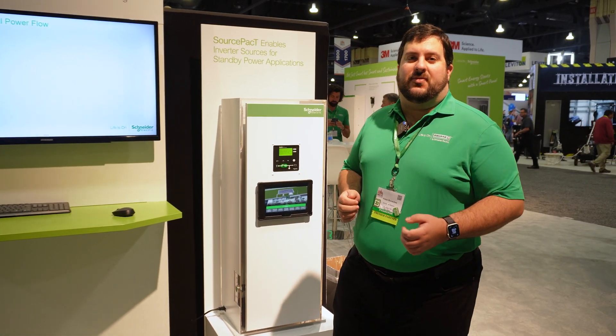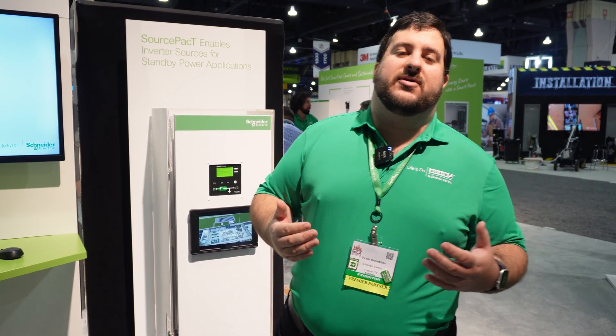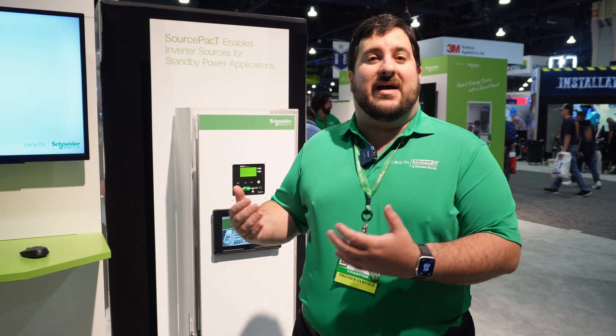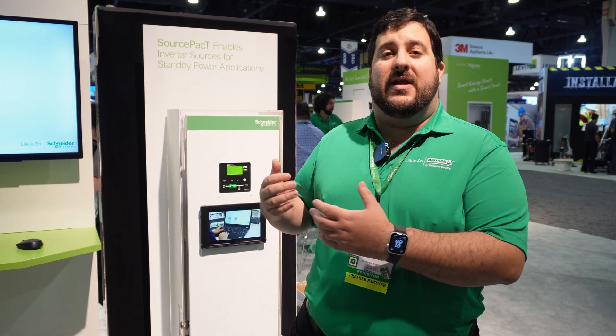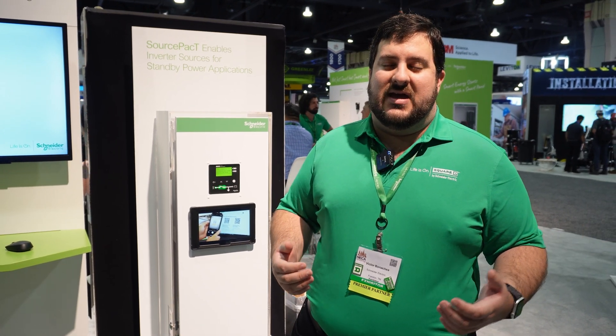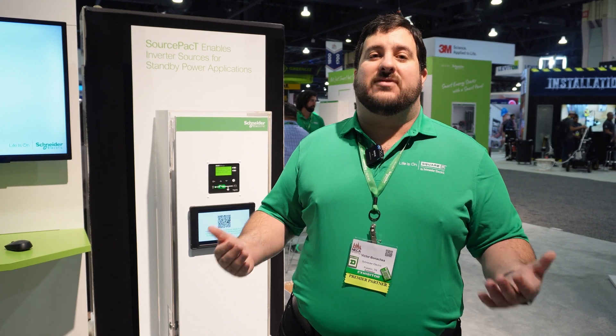Hi, my name is Victor Bonaccia. I'm the product strategy director with ASCO Power, which is a business unit of Schneider Electric. I'm here today to talk to you about SourcePacT, which is really meant to solve an issue that contractors are facing - where they're having to put together their own solution to provide isolation from a utility for a battery energy storage system, so that they can use those same battery energy systems as a backup power source. A lot of people are under the impression that if they have solar and batteries, they can use it as a backup source if power fails from a utility, but it's actually not that straightforward. You need to provide the right isolation and controls to make sure those other sources from the inverter are not backfeeding the utility for safety and compliance issues. A lot of contractors are self-assembling their own solutions using parts from all sorts of different manufacturers, and that's very difficult. There's not much standardization in this new energy landscape yet, and that's what we're working to resolve.